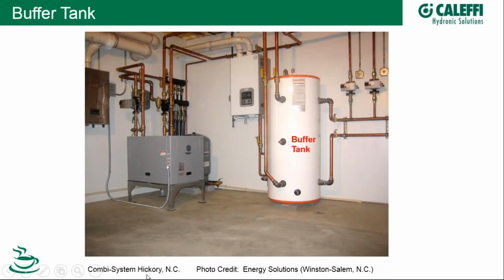It's a combi system. So what we have here is a buffer tank, and off to the right we have our secondary. So coming off the top of our buffer tank, heated water going out to, I think there's 8 different zones up to our building, coming back on the return header back to the buffer tank. Now this is the secondary side, okay? And by way of the buffer tank, having all these, at least 4 ports, these pumps now are decoupled. They don't see each other.